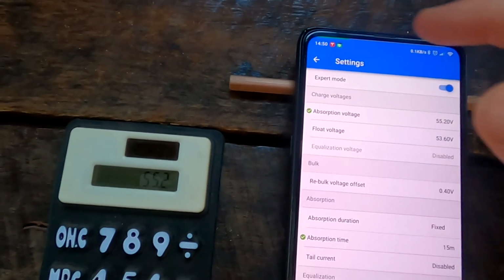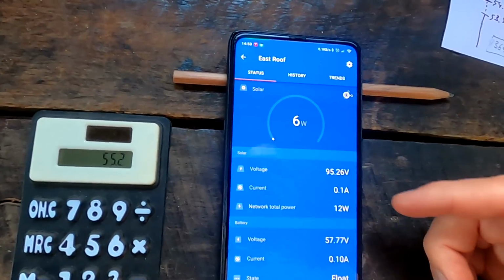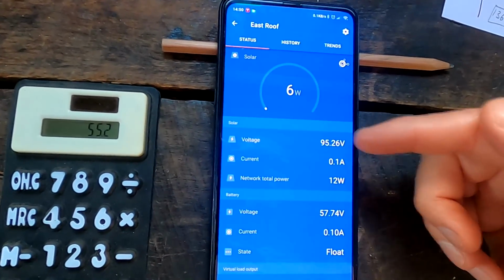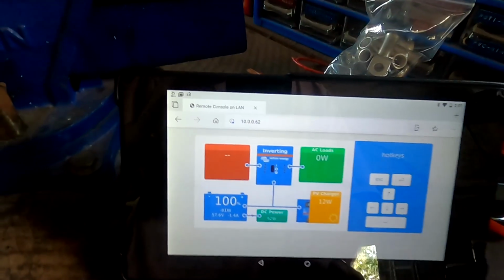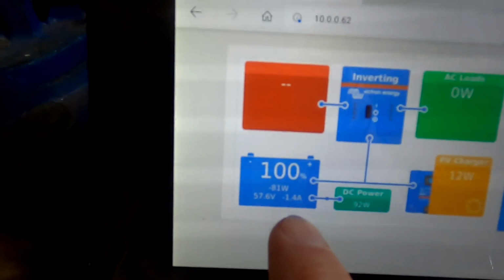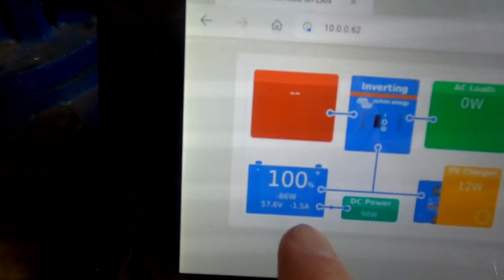Green tick, all good. Yeah, both charge controllers will turn off at the moment because the voltage is far higher than we set. And from now on, it will only discharge the battery. We can see 1.5 amps going out of the battery. And then we will check again how many ampere hours we have actually used from 100% state of charge to our float voltage of 3.35. That'll be the first test to see how much capacity is actually in between. So I guess this will take now 15-20 minutes and then we should hit the float voltage.